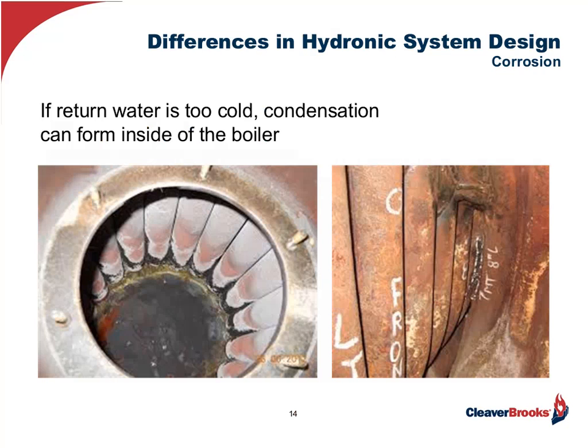because the higher the excess air level, the lower the dew point of that gas. Anyway, the other thing, though, really critical with these is when they condense, those fins will plug. And when they plug, you develop back pressure in the furnace, and you go to a very, very rich mix of the gas. You start to soot up and causes all sorts of problems. So what we're talking about here is extremely important. When you've got a boiler that's non-condensing or near condensing, you've got to take a look at those temperatures. You've got to take a look at those flows, or you're really going to have problems. So now let's go to the Q&A, if you would, please.